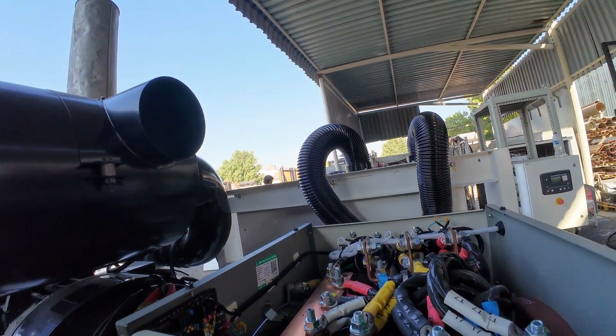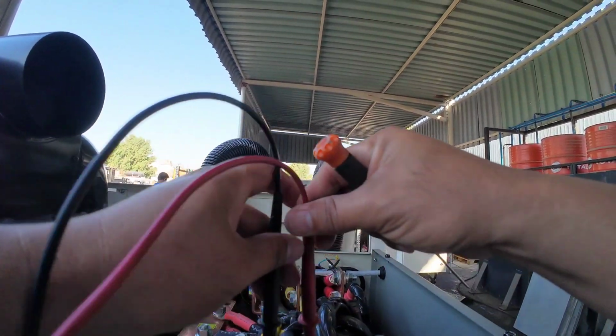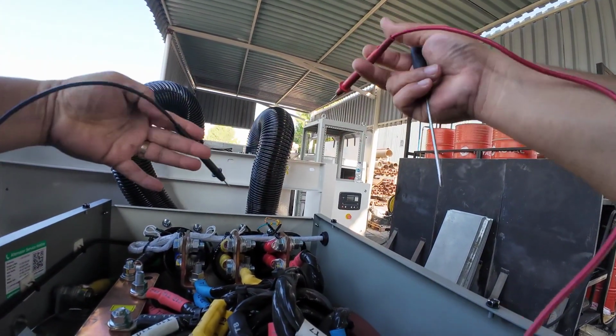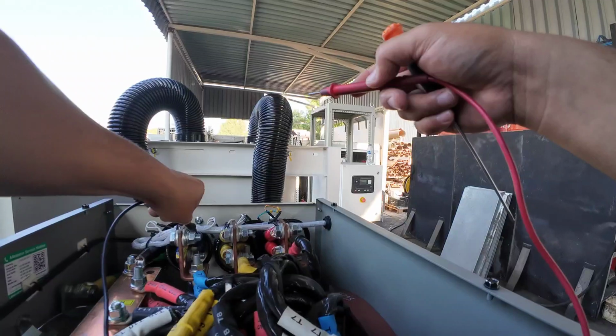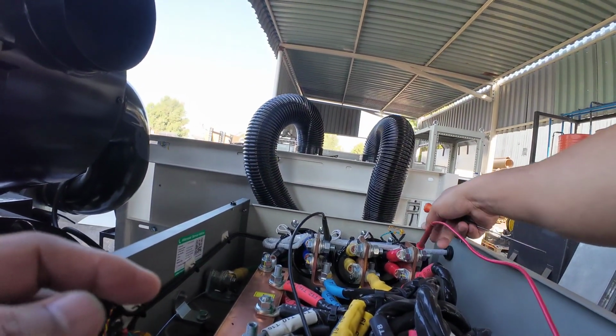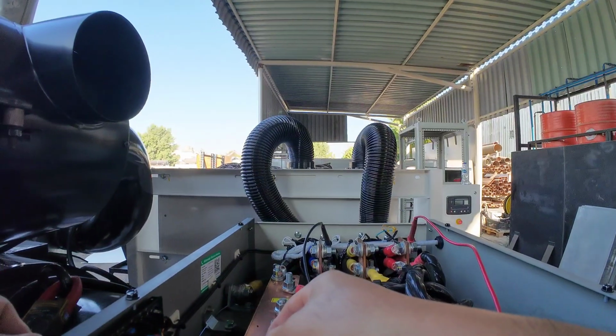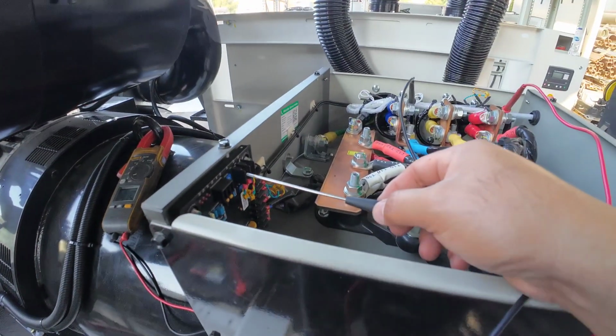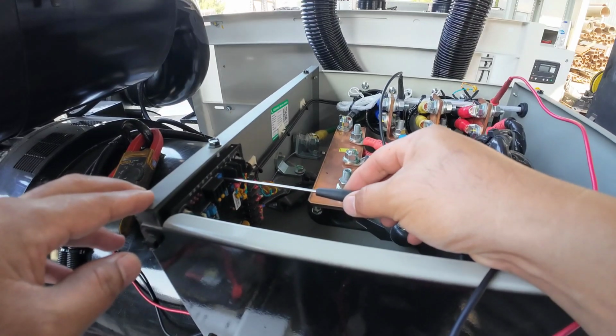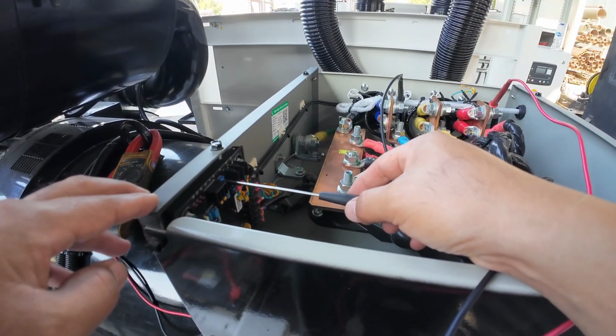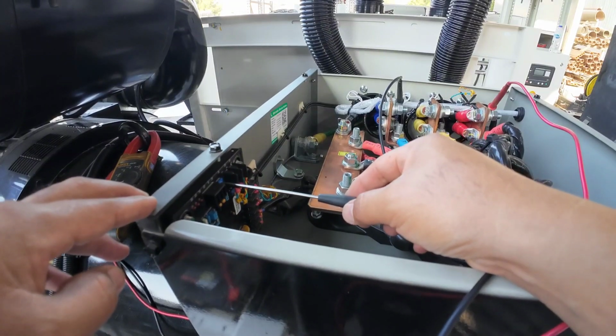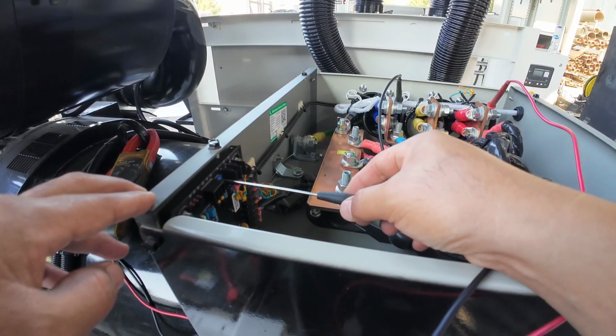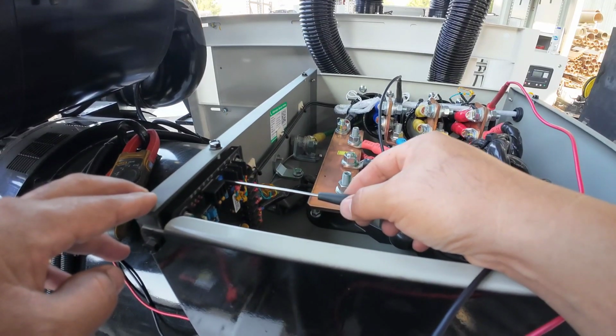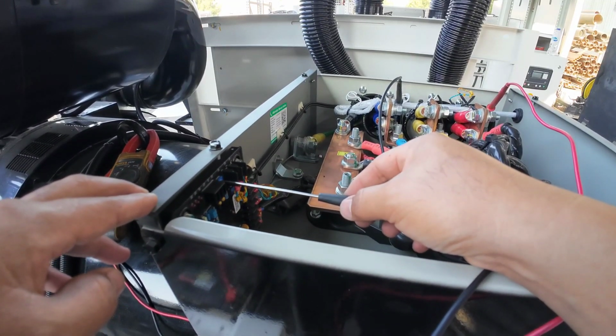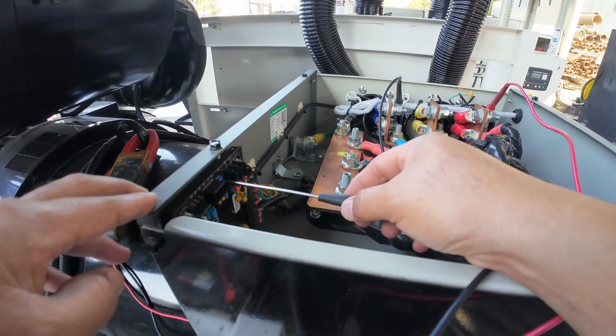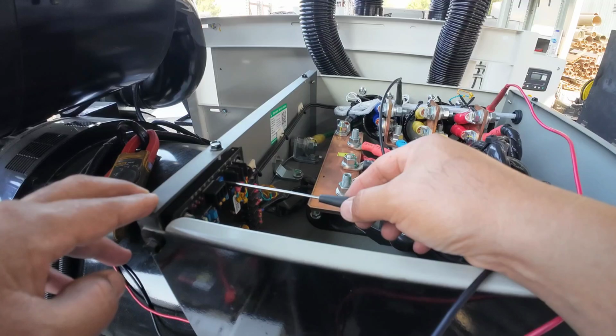The AVR voltage calibrations - in order to have a good percentage for our voltage control, we need to catch 75% full control for our AVR, so we have good command for our module. If there is some instability, low voltage, or high voltage, it will be managed to control at that maximum percentage for our AVR. You don't have to worry - once you get this percentage, you have full control of the voltage.